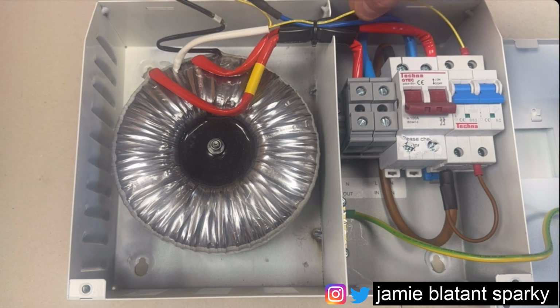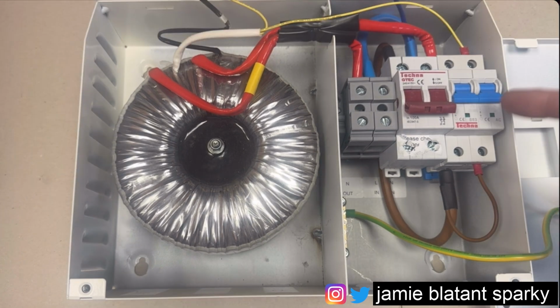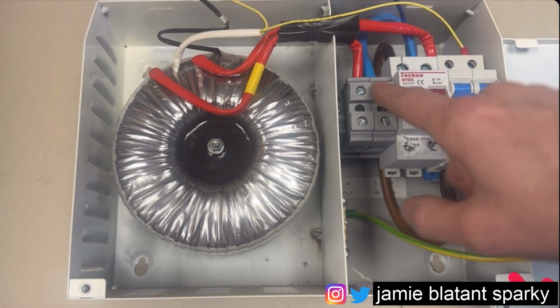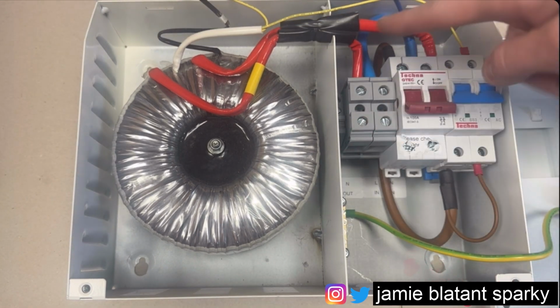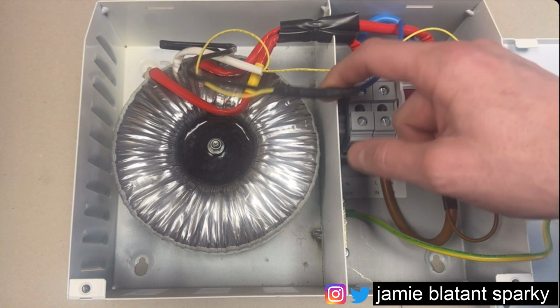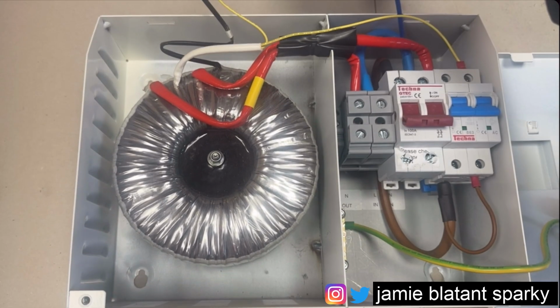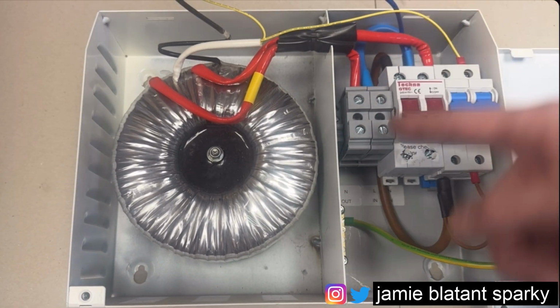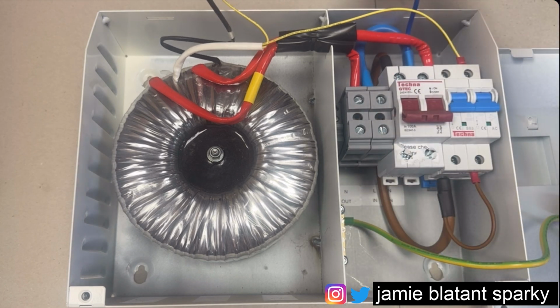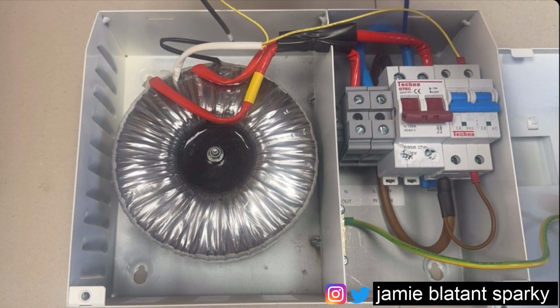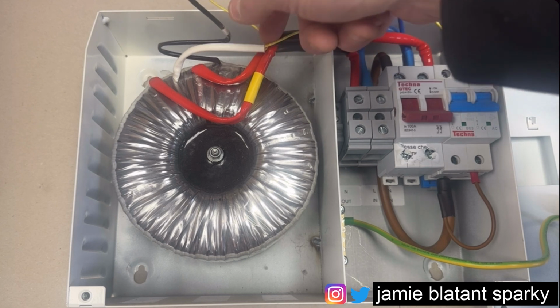It's there, look. Let's cut these off. We'll face the fact that the neutral just goes straight through - it passes directly through, but there's a little lead here. Let's go up a bit, look. So the neutral doesn't go straight through - most of the neutral does, but there's obviously some sort of reference here, and that goes down this cable here, into this little cable.